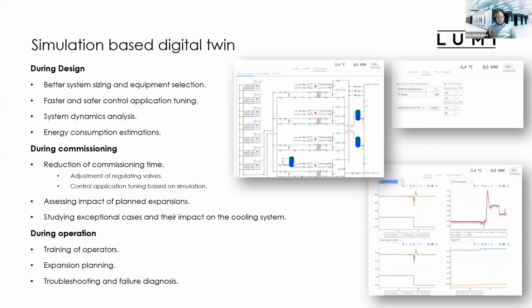We could do faster and safer control of application tuning. So our building management system tuning could be done beforehand, even before there were any cabinets installed in the data center. We could do system dynamic analysis, and we could do energy consumption estimations. During the commission phase, this had a major effect, reduction of the commission time. So we could do the adjustment of the regulation valves. We could control the application-based tuning on this simulation.